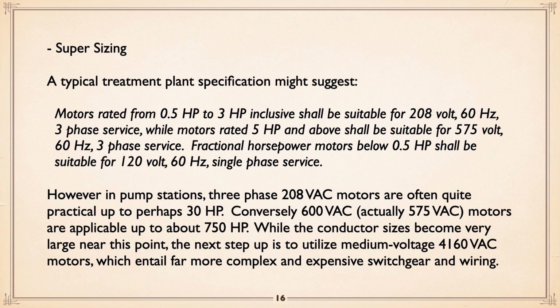That's always been an argument. Where do you draw the line? And I got advice from somebody who had a lot of experience in it, who suggested 600 volt up to about 750 horse. You can scale that back a bit if you're running 480. The reason being, well, the conductor sizes get very large. In fact, you end up kind of duplicating services. Instead of 3 lines going to the motor, you've got 6, carrying each of line 1, line 2, line 3 on 2 wires.